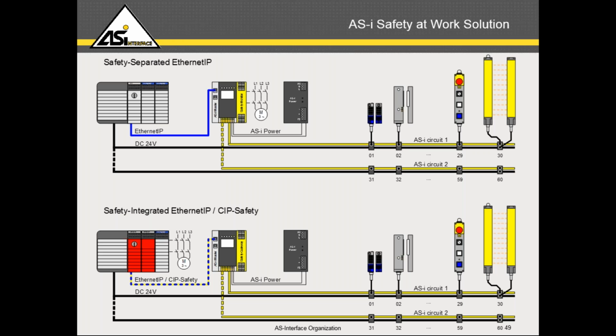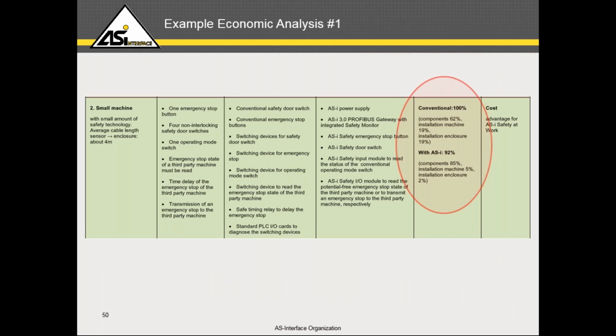So there's many ways of providing a complete solution for the AS interface. Of course, the idea of ASI stops at the yellow cable, but you also have a gateway communication that talks to the higher level PLC as well. And some of the PLC systems, as I showed you in the first example, have built-in communication and can work as an AS interface master monitor module as well.